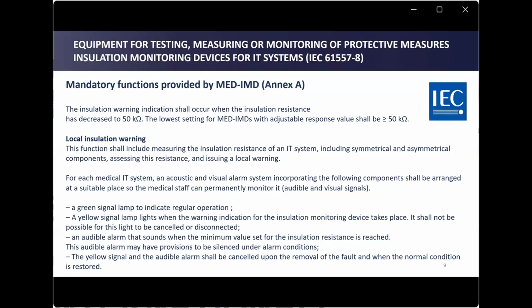For each medical IT system, an acoustic and visual alarm system incorporating the following components shall be arranged at a suitable place, so that it can be permanently monitored by the medical staff. A green signal lamp to indicate normal operation, a yellow signal lamp which lights when the warning indication of the insulation monitoring device takes place. It shall not be possible for this light to be cancelled or disconnected. An audible alarm which sounds when the minimum value set for the insulation resistance is reached. This audible alarm may have provisions to be silenced under alarm conditions. The yellow signal and the audible alarm shall be cancelled on removal of the fault and when normal condition is restored.